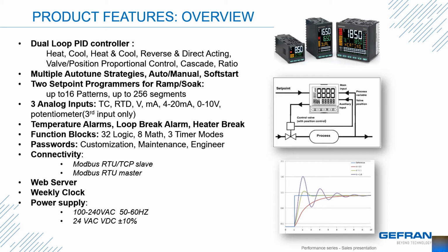You have multiple PID tuning methods, auto manual control, soft start, up to 16 ramp soak programs can be stored with up to 256 segments. There is a third analog input available. It has specific functions for things like remote set point or valve position feedback. We have multiple temperature alarms and types, loop break alarm and heater break alarm. The function block programming includes up to 32 logic blocks, 8 math blocks, and 3 timer modes.